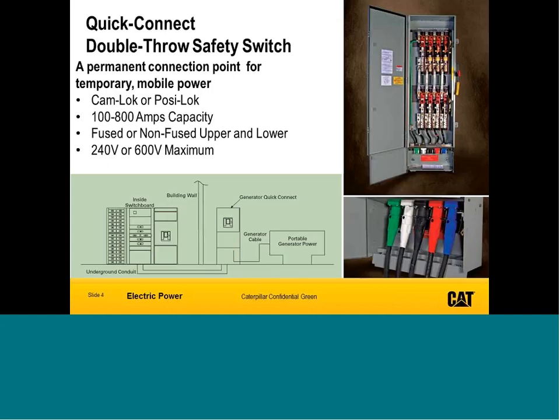If you wanted to go a little bit above and beyond that, what I'm showing now is what we call a quick connect station. This is an extension of your electrical distribution system that you'd mount in a weather-protected enclosure outside of your building. In the lower right, you're seeing cam lock connections, standard on 4-aught or 1-aught cables, which let you connect the mobile generator into your facility as close to plug and play as possible.